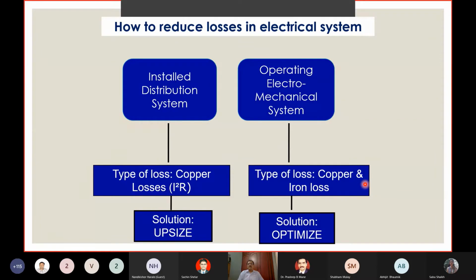Now, how do we reduce the losses in the electrical system? A simple rule of thumb has been suggested here. In the installed distribution system, the losses are basically I²R losses or line losses. So what are we left with? We can't go and reduce the I. When you suggest to the process to reduce I, you are suggesting they reduce the productivity. You can't reduce productivity in order to achieve electrical efficiency. So you have to ensure that this I is not reduced, but the R can be reduced. R is resistance. How will you reduce R?